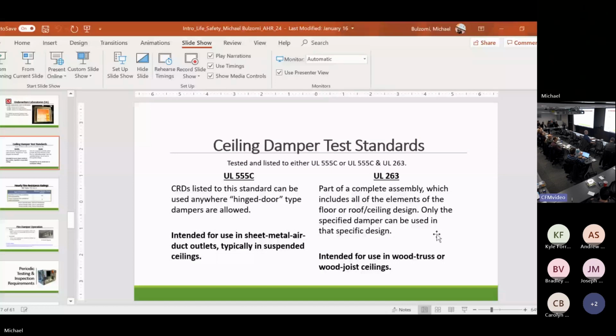L521 is a proprietary number owned by a damper manufacturer. That damper manufacturer was very smart. They cornered the industry. They did groundbreaking testing and got the first listing for combustible wood truss with an HVAC penetration. And then they went to UL and said, we own this. Anybody else who wants to do this has to test and list to their own number. We're going to market the heck out of L521. We're going to go to every architect and drill it into their brain: specify L521.